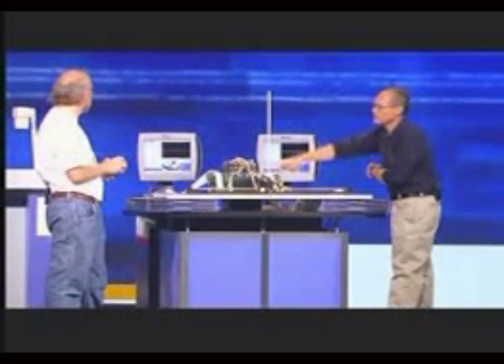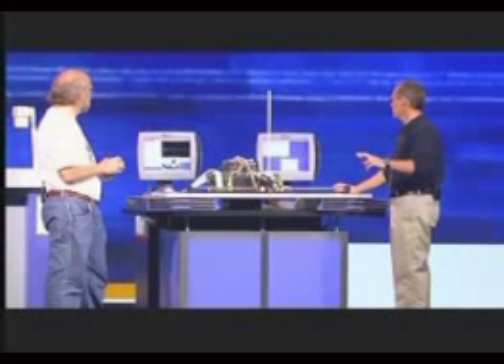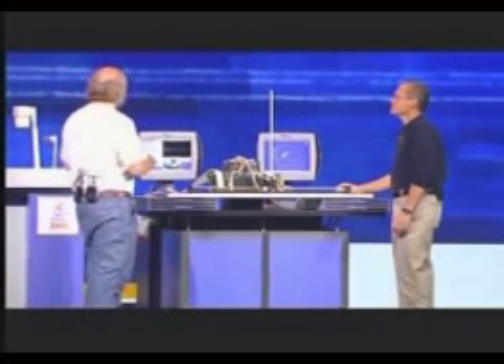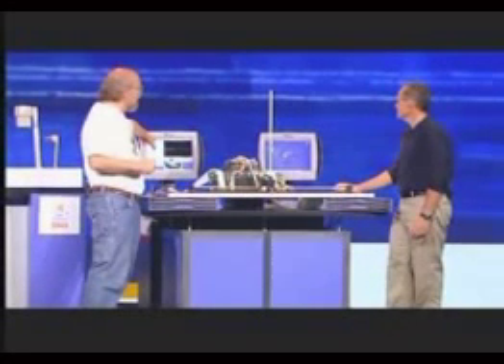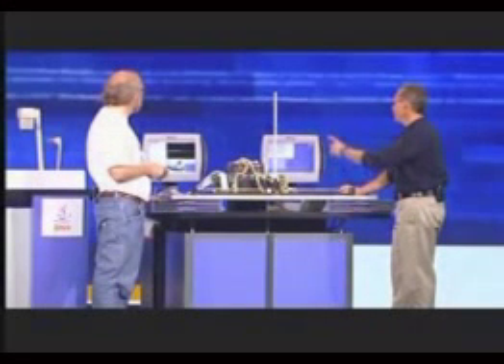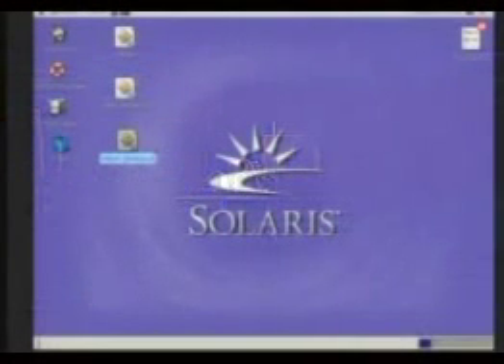I'm going to make sure the backup is ready to take over. The backup is following — reading the encoders, computing — but it's not writing. Now kill that VM. The left one takes over. That one went from backup to active. Let's relaunch that server and start it in backup mode. Now fail that one. It failed. This one took over, then just passed back over again.